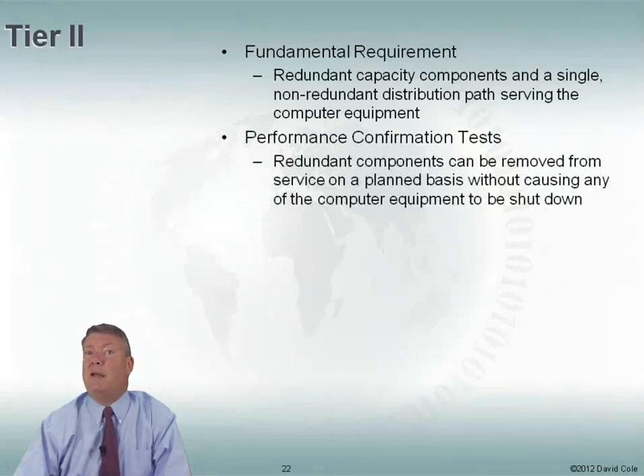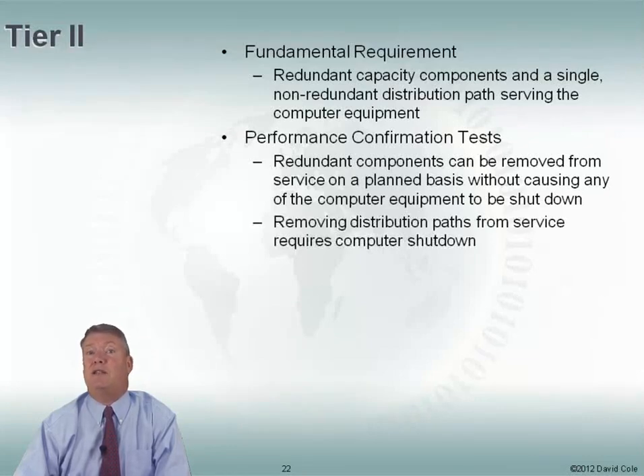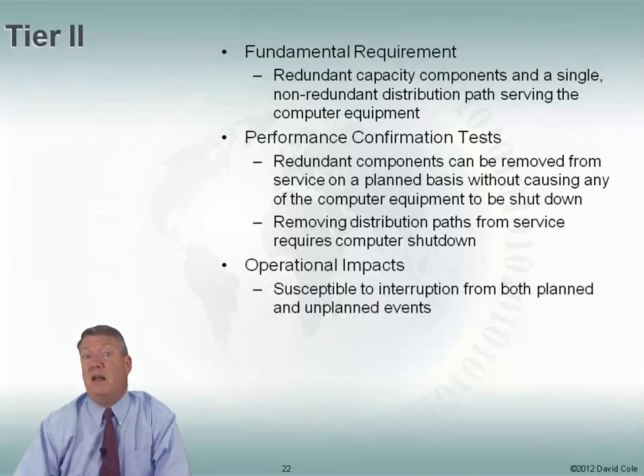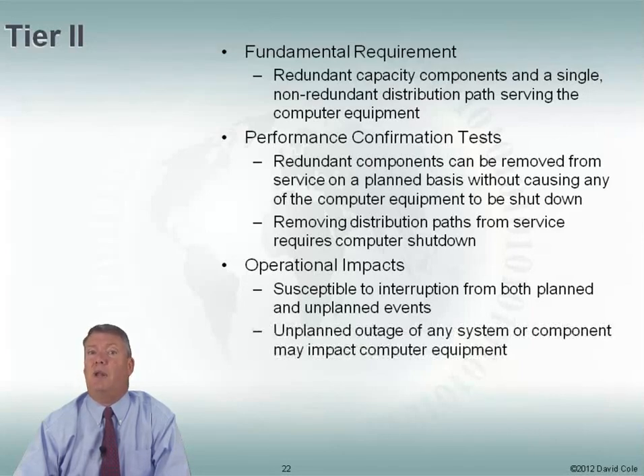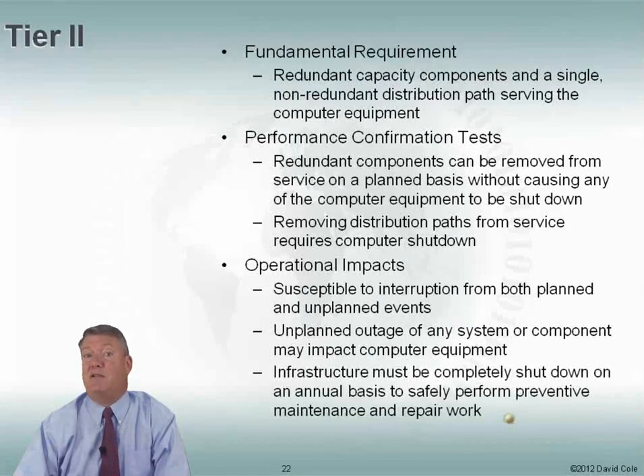This means I can remove my redundant components on a planned basis without shutting down my computer room equipment. For example, I can do maintenance on one of my CRAC units without worrying about having enough cooling. My distribution path, however, my electrical path, would still require a shutdown. The operational impact is that I'm still susceptible to interruption from both planned and unplanned events, and any unplanned outage may impact my computer equipment with some downtime.